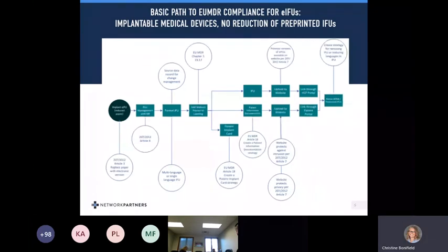Lastly, if your product meets the criteria of 207-2012, you may be able to remove the paper IFU from your package once the e-labeling requirements are met. For those of you unfamiliar with 207-2012, this is the regulation allowing for e-labeling in the EU. Beyond the 3 website requirements needed for the basic eIFU required by the MDR, there is a whole laundry list of website requirements for e-labeling, like a toll-free number so people can call to request a printed copy, that printed copy mailed to a user within the acceptable time, safety and backup systems, limited system downtime, and some more things to make sure that the information is available to those that need it.